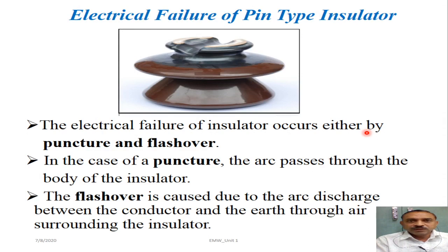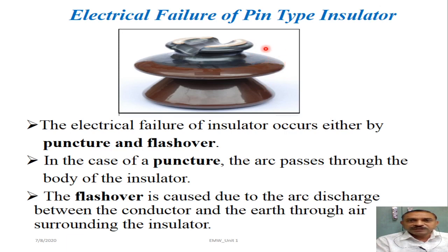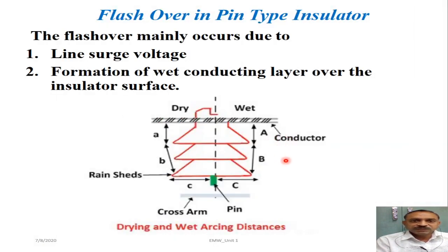Electrical failure of a pin type insulator will be either through puncture or flashover. In the case of puncture, the arc passes through the main body of the insulator when electric stress rises to a very high value. The second case is flashover, which is caused due to arc discharge between the conductor and the earth through the air surrounding the insulator.